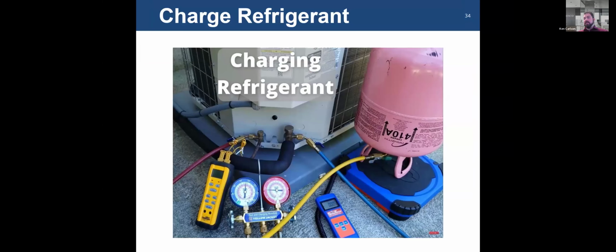So, refrigerant charging. As we talked about before, equipment often comes pre-charged. If you're doing service work, you would need to charge it. If you've got extra line set, you will need to add additional charge. You will need a scale, as shown here, a set of gauges, and something to measure temperature, whether it's a thermistor or a thermocouple, to measure the temperature of your discharge and suction lines.